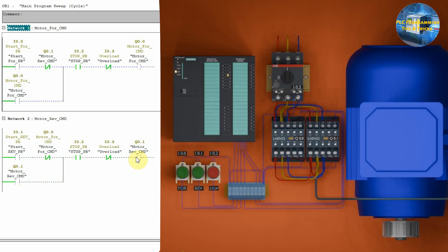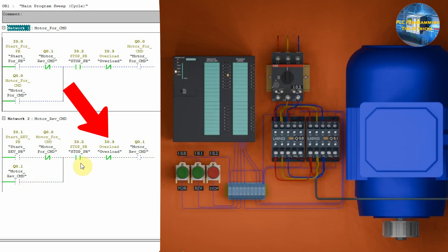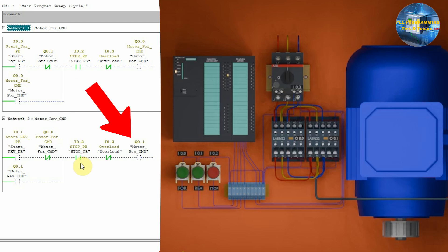This Q0.1 output will be latched on through its own normally open contact Q0.1 through this path. Next, we have a normally open contact I0.2 of the stop push button and a normally closed contact of overload I0.3 in series with the motor reverse command Q0.1.